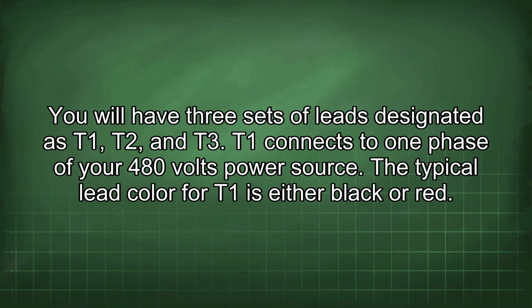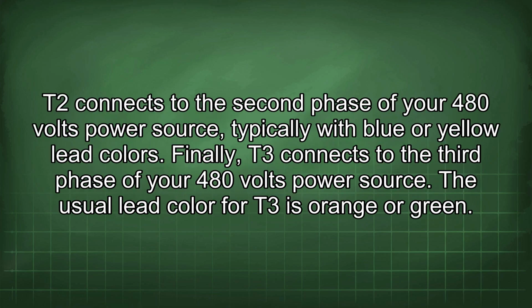You will have three sets of leads designated as T1, T2 and T3. T1 connects to one phase of your 480 volts power source. The typical lead color for T1 is either black or red. T2 connects to the second phase of your 480 volts power source, typically with blue or yellow lead colors. Finally, T3 connects to the third phase of your 480 volts power source. The usual lead color for T3 is orange or green.